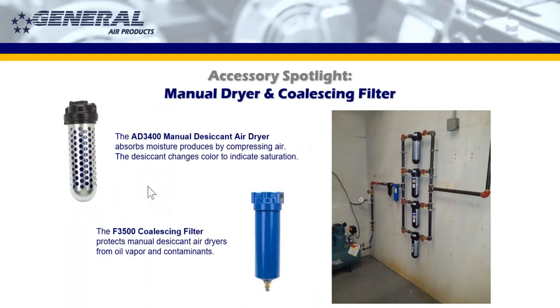The AD3400 is a manual desiccant air dryer. So you can see how the assembly is hooked up there. Oftentimes, people run a bypass valve or a bypass line to go around it. So at certain times of the year, let's say the summer, the spring, and maybe part of the fall, they just run the compressor regularly, but they don't want to get any ice plugs in there, for example in a parking garage in Boston or Minneapolis. Then during the winter, when it gets below freezing, they switch it over to manual desiccant dryer mode, and it goes through there.